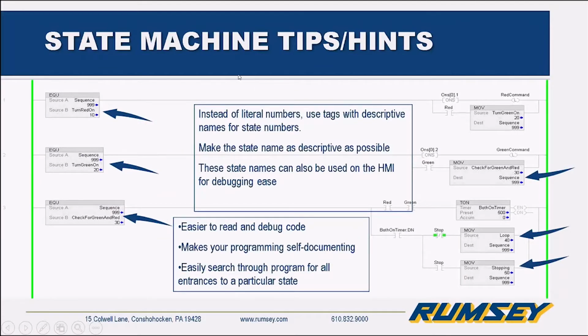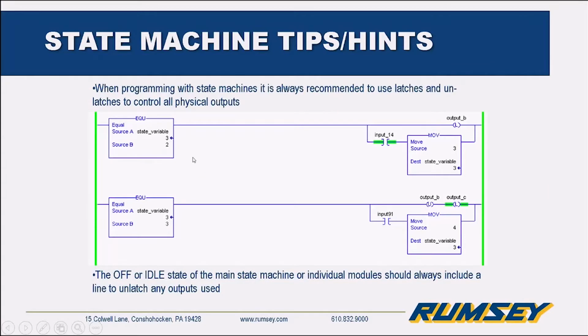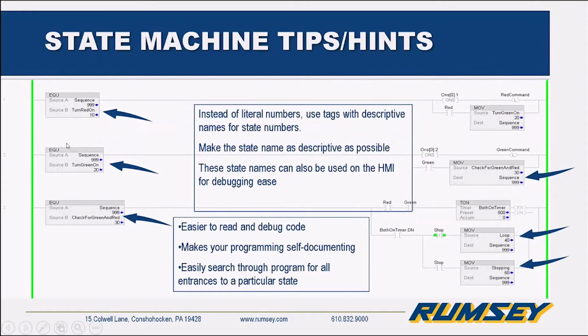Another big takeaway for the self-documentation portion of this: instead of using individual numbers, as in the previous slide, use tags with descriptive names, and then your code becomes self-documenting. The sequence being, this is our state variable, is it equal to 10, which happens to be turn red on. That is easy for troubleshooting because I can right click and do a cross reference and see where all turn red on is used, or where all turn green on is used, rather than trying to search for the number 10. The number 10 could appear almost anywhere, or number 11, whatever number it is. The point being that the tag will take you to the rungs that are using that particular tag in your state machine, and it does self-documentation and makes it easy for troubleshooting purposes.